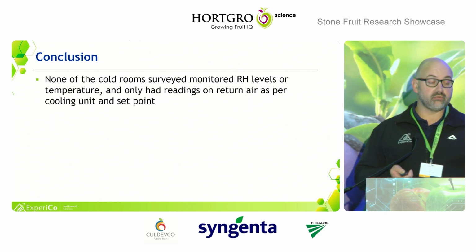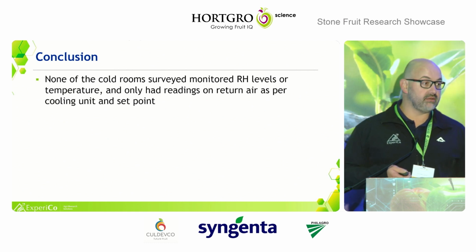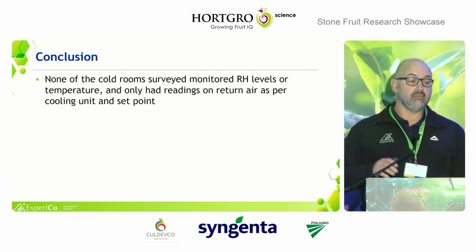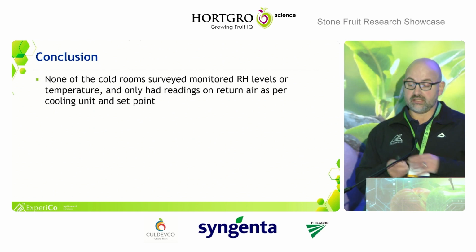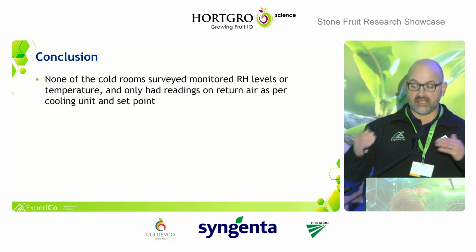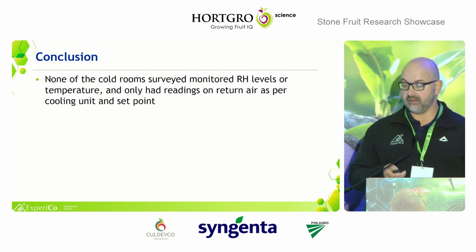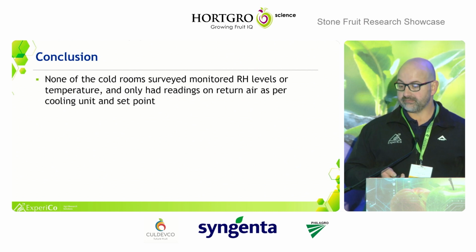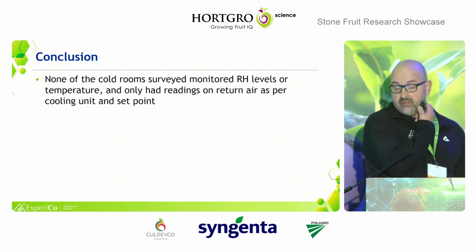None of the cold rooms that we surveyed monitored the relative humidity levels or the temperature with a dedicated system. They can only see the set point that the cold room is set at and the return air, as per the cooling unit and set point.